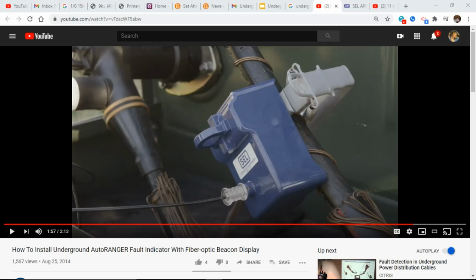What we would do is in our install, we would not even put those two strands underneath. Now you're going to have to ground the elbow. It's got a static ground on it. We would take those two strands, follow my mouse, and go around the outside and then ground the elbow. Now all I am measuring is the magnetic field. The fault current that goes through is the magnetic field of the core of the wire. That is a good thing.